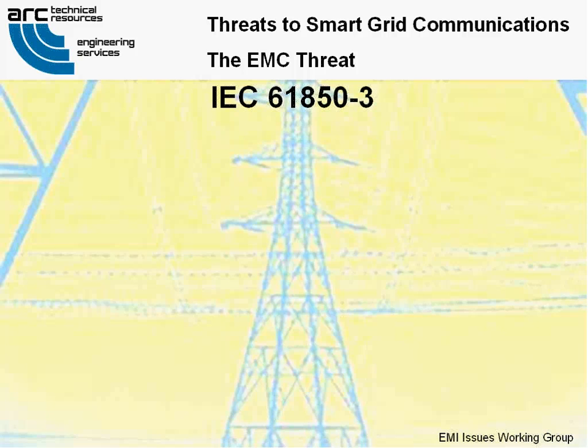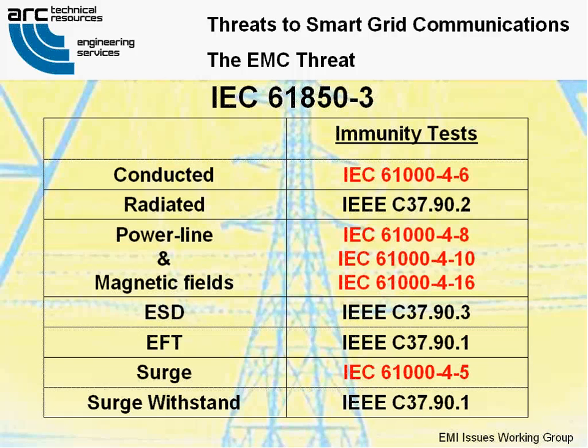IEC 61850-3 requires these immunity tests shown on the right. IEC 61000-4-6, conducted RF immunity. IEC 61000-4-3, radiated RF fields, covered by C37.90.2. IEC 61000-4-8, power frequency magnetic fields. IEC 61000-4-10, damped oscillatory magnetic fields. IEC 61000-4-16, conducted common mode disturbances. IEC 61000-4-4, EFT, covered by C37.90.1. IEC 61000-4-5, surge. IEC 61000-4-12, ring wave, and damped oscillatory waves, which is covered under C37.90.1.